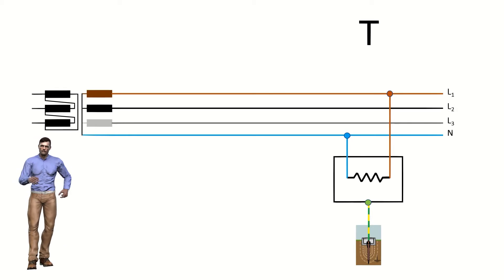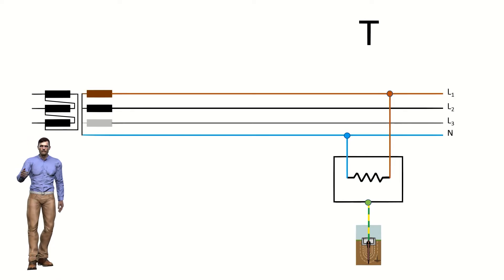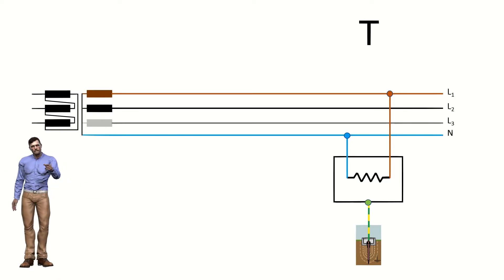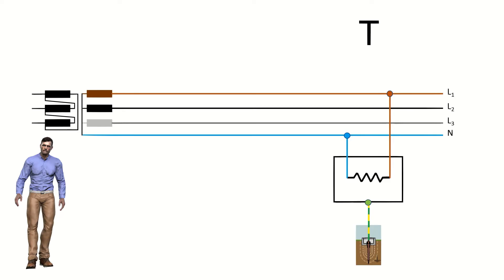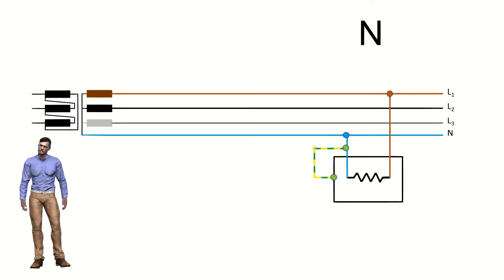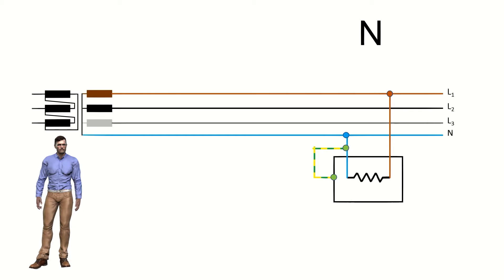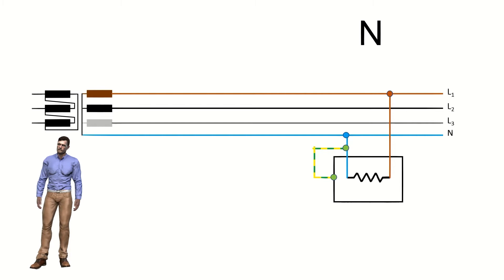For the second letter, which indicates the type of connection in relation to ground of the masses of the customer's loads, that is, their metal enclosures, we use the letter T if these are connected directly to a ground independent of the one of the distribution system. The second letter can also take the value N, in case the masses of the loads are connected directly to the grounded point of the transformer, which for a three-phase installation is normally the neutral.